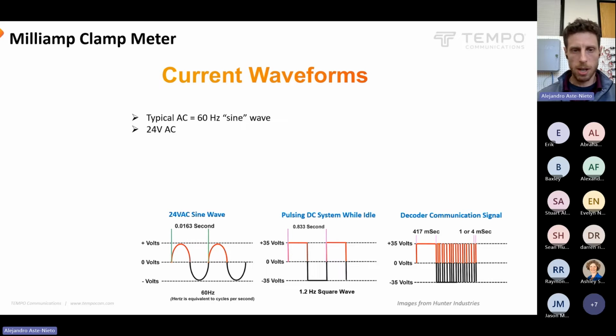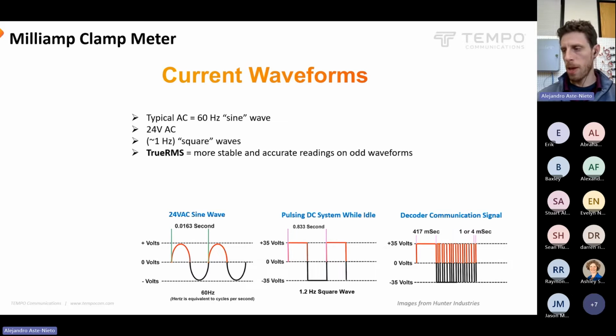Other systems will use very odd waves that might be very slow, like one time per second. It'll switch back and forth between positive and negative voltage between the two wires. So, for instance, the Hunter ICD system will be 1.2 hertz of a very square alternating current wave, a very different wave than what's typical out there. The good thing is true RMS, which is built into the CMA 360B, will make good sense of waveforms that are not very smooth like this. Most meters out there just assume this is the shape of the wave and do rough math to give you a current number, but this actually calculates for any kind of waveform. So that's helpful for two-wire, obviously.